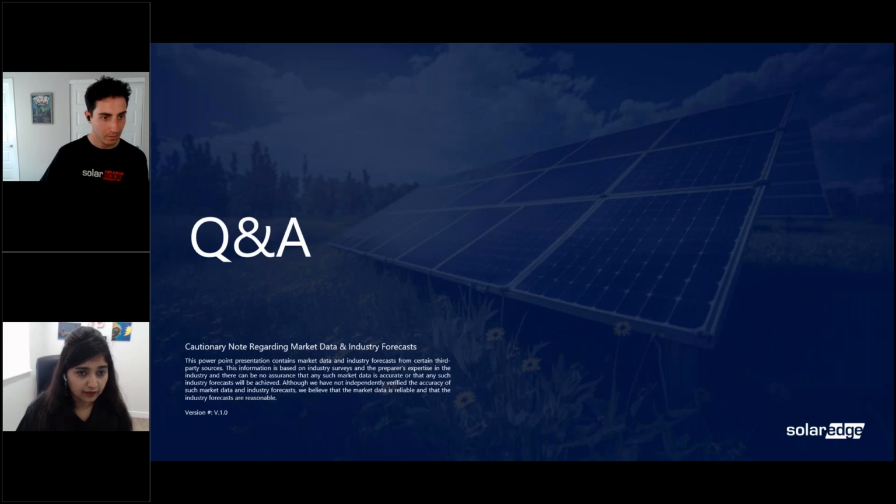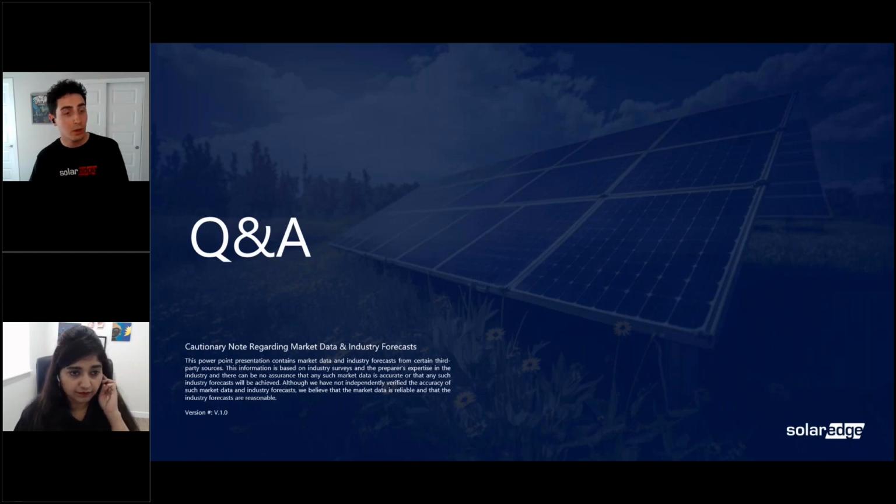Got it. Thanks, Jacob. There's another question by Peter to explain the additional structural requirements that are required with the non-DC optimized solution. Oh, sure. So basically protective raceways, specialized zip ties or cable clips to maintain a certain amount of spacing from your home run strings to the conductive parts of the racking system, things like that.